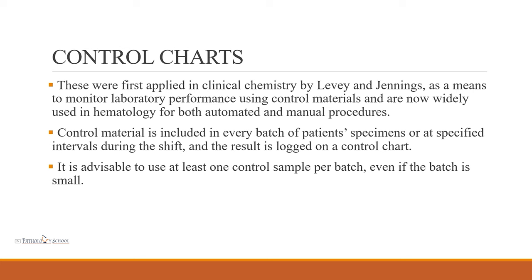Control charts were first applied in clinical chemistry by Levey and Jennings — hence the name LJ chart. They are a means to monitor laboratory performance using control materials and are now widely used in hematology. These charts are obtained on automated machines or can be plotted manually. Control material is included in every batch of patient specimens or at specified intervals during the shift, and the result is logged on the control chart. It is advisable to use at least one control sample per batch.